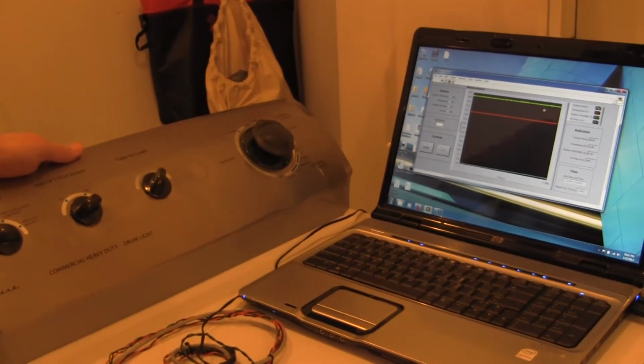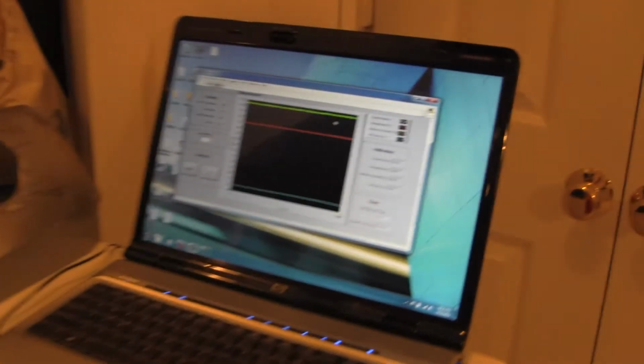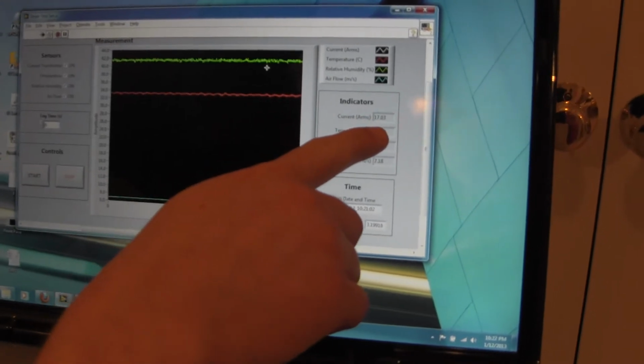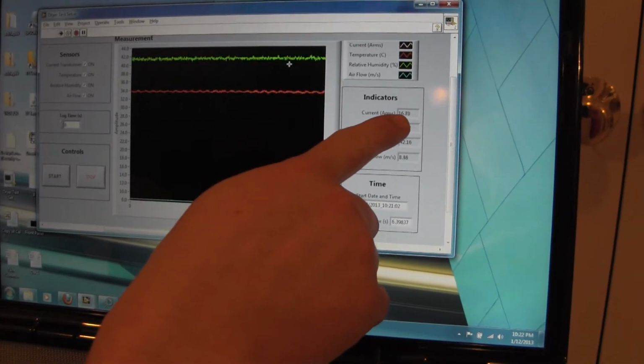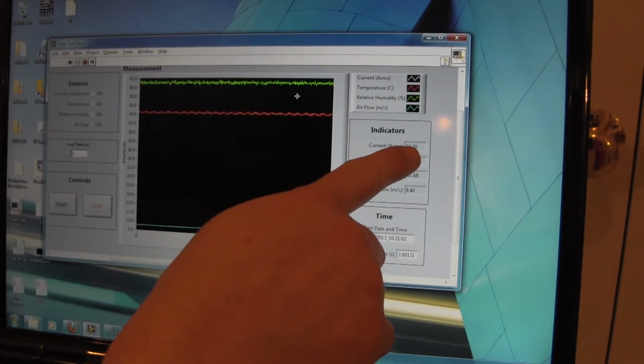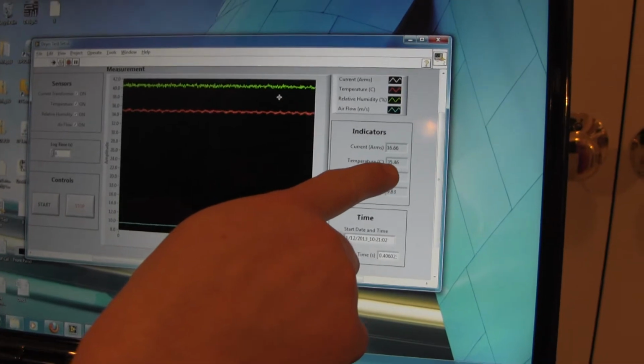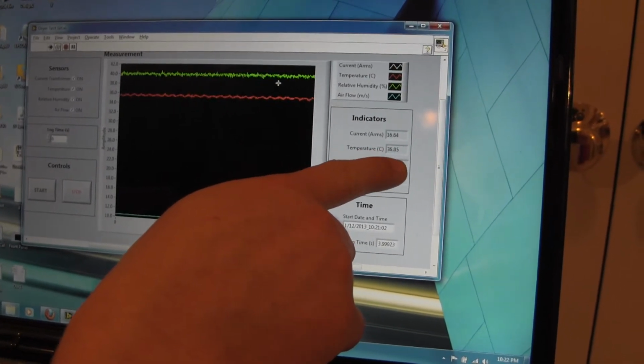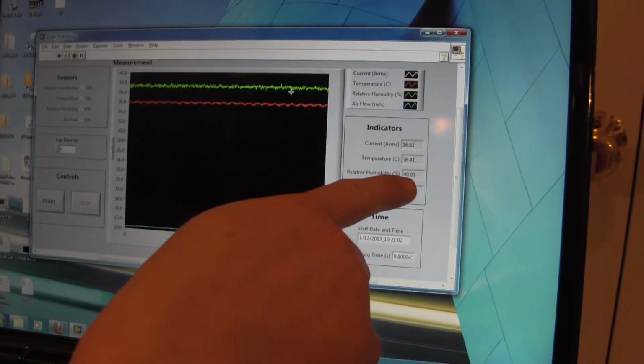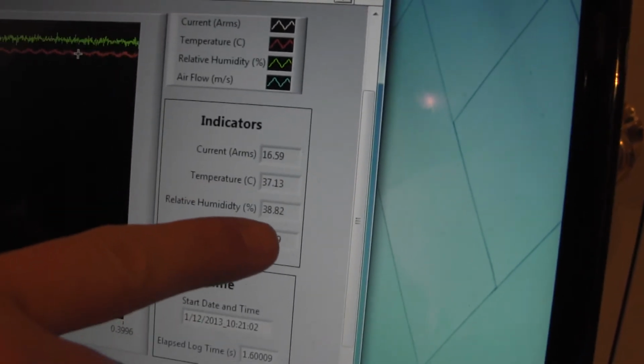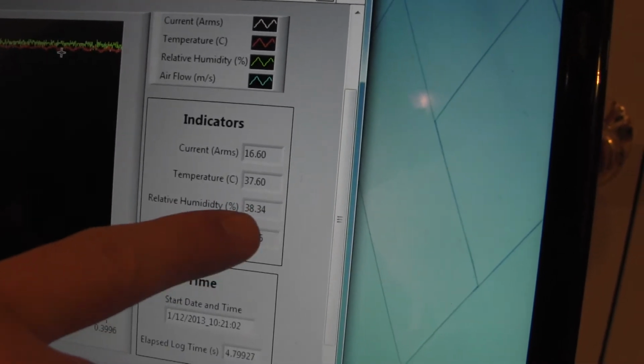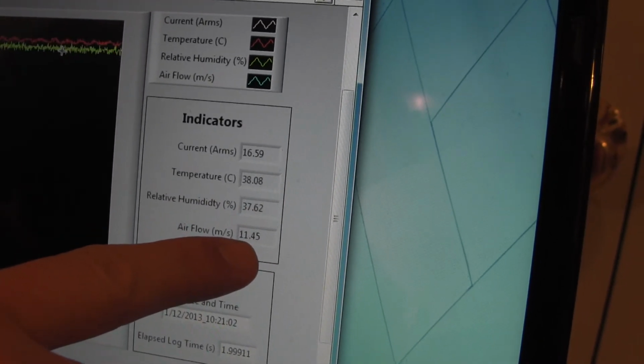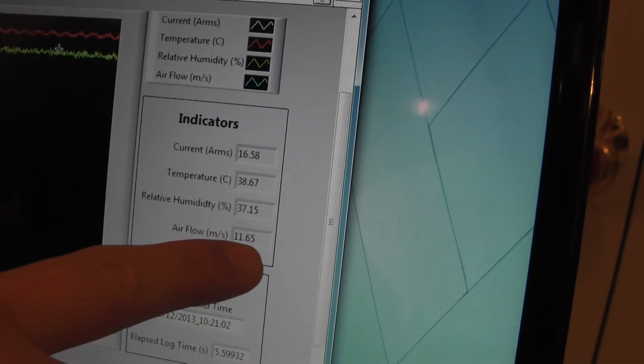turn on our dryer. If you noticed, our current has gone up to 16.8 amps RMS. Temperature is about 35.8 C, it's climbing, 36. The relative humidity is pretty much the same because the clothes that are in there are dry. If the clothes were wet, this would be a much larger number. And the airflow is at 11.68 meters per second. And here we have our start time and date, and this is a counter.